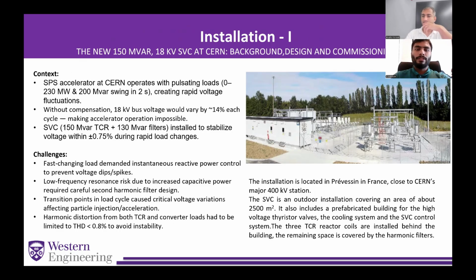So our first case study is an installation in France at CERN power station. The main issue in this substation was that there was a fluctuation of 14% in voltage in each cycle on 18 kilovolt bus. So to cater to this problem, they installed an SVC. This fluctuation was due to the fast changing loads which demand reactive power and harmonic distortions. Can you go to the next slide, please?